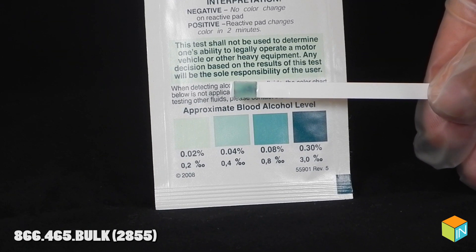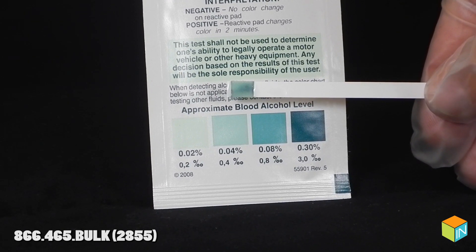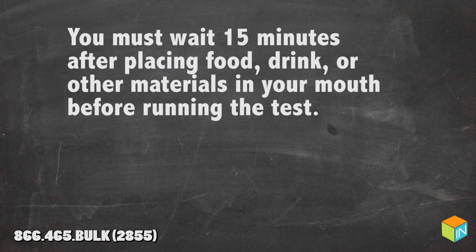Commercially available controls that contain preservatives cannot be used with the AlcoScreen. As a general rule whenever conducting this test, you must wait 15 minutes after placing food, drink, or other materials in your mouth before running the test.